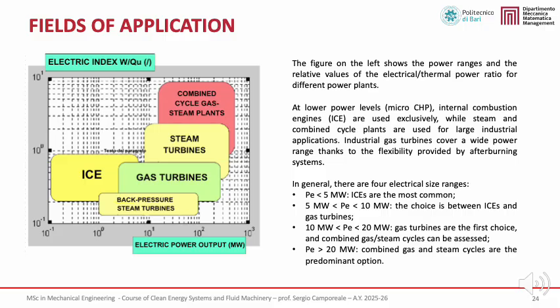As we move toward medium power levels, industrial gas turbines become increasingly attractive. They cover a wide power range and allow flexibility in the electric-to-thermal ratio, particularly when afterburning systems are used to enhance heat production. At higher power levels, steam turbines and, above all, combined gas-steam cycles become the preferred option. These systems are typically adopted in large industrial applications, where continuous operation and high power output justify the increased complexity and capital investment. As summarized on the right-hand side, 4 main electrical size ranges can be identified. Below 5 megawatts, internal combustion engines are generally the most common choice. Between 5 and 10 megawatts, both internal combustion engines and gas turbines can be considered.